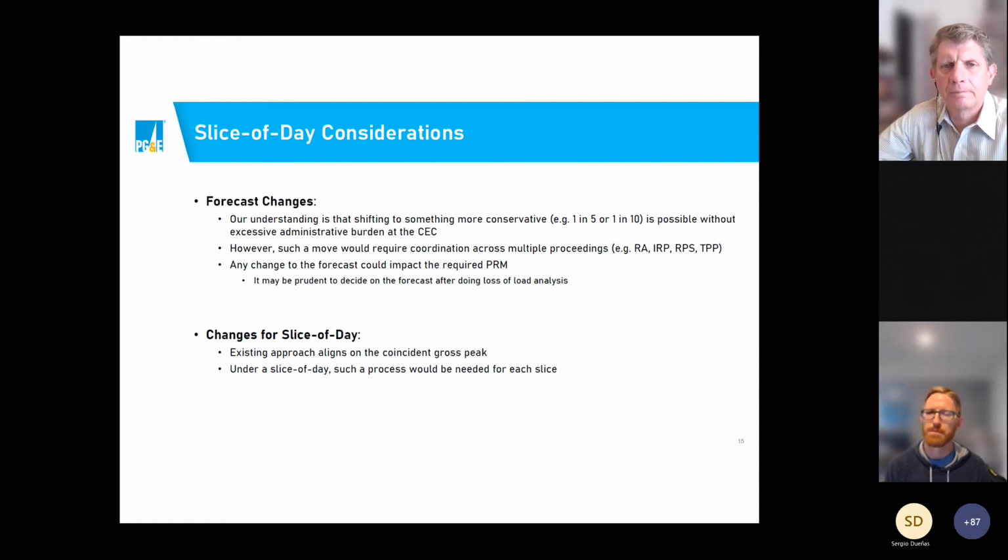So do we socialize the cost of that maintenance across the system, everybody buys a little excess, and then the CAISO could relax its rules around having to have that substitute capacity up front, because the PRM already accounts for it, and we would just be doing studies to make sure you're only matching whatever planned outage you assumed for that period, especially if we maintain the monthly construct.